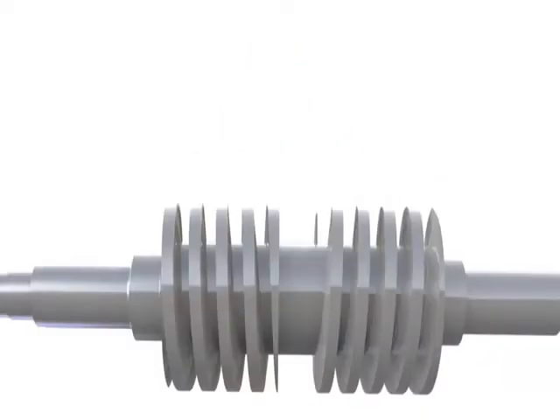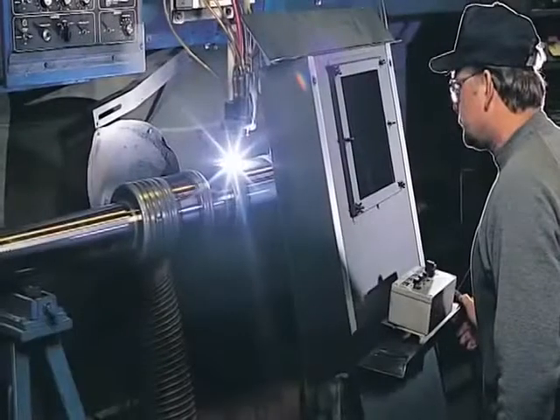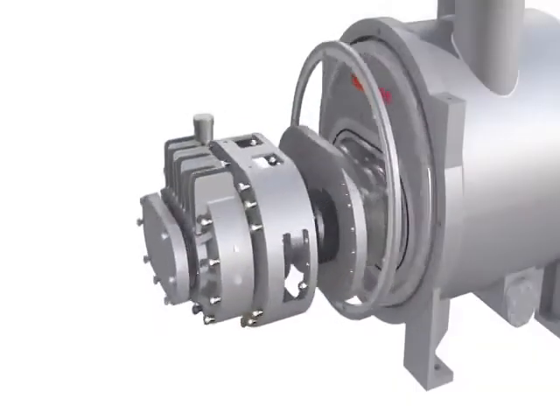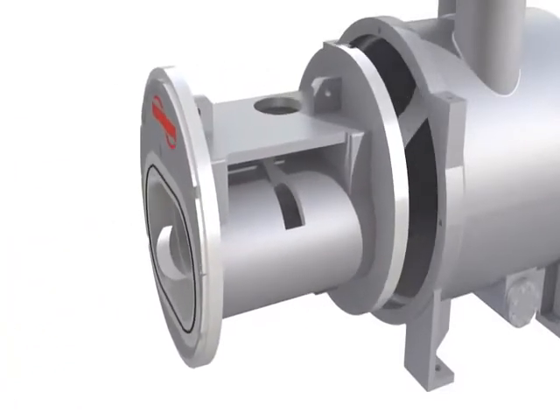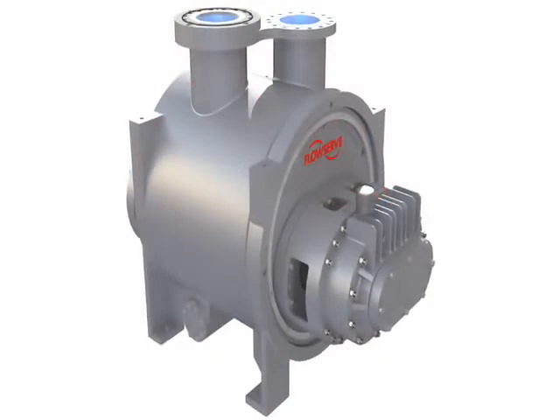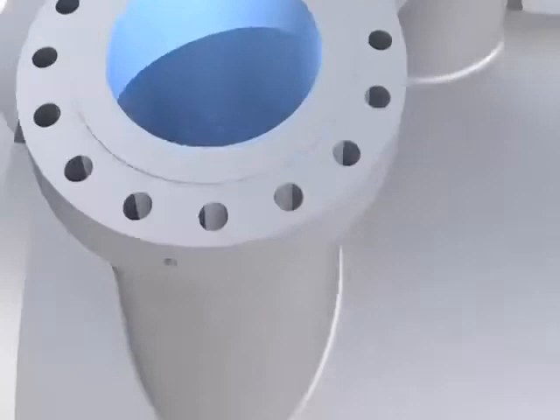The design also provides excellent volumetric performance when handling multi-phase compositions. The MP1 screw pitch can be customized in 3mm increments for high efficiency operation. A hard tipping overlay is ideal for services with high concentrations of sand. The MP1 is designed with a two-piece casing. The inner casing is chrome plated for increased abrasion resistance and can be easily replaced should wear occur over time. Pump nozzles are integral to the outer casing, so the inner casing is not exposed to any pipe loads, ensuring non-contacting rotor operation.